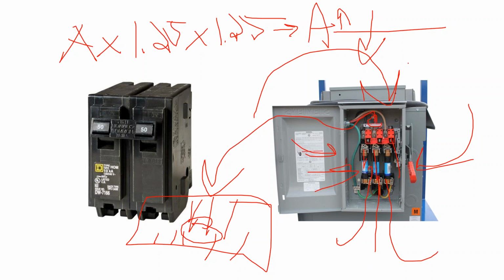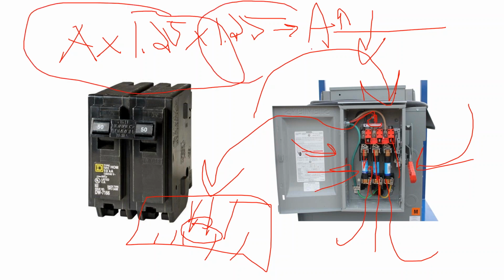And the installer thought, well, normally this fuse will never get up to 10 amps, so a 10 amp fuse will be fine. This calculation might give you 10 amps, versus the additional safety factor giving you another. Regardless, I got called out to site to troubleshoot an array, and it turned out that the fuse in the fuse box was too small to accommodate this additional 25%.